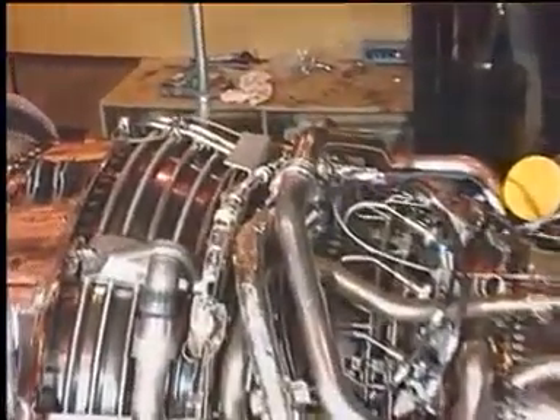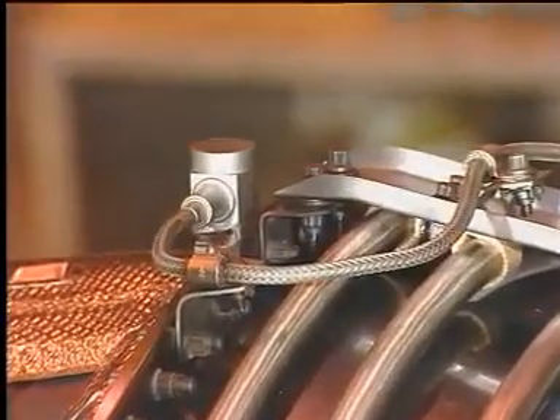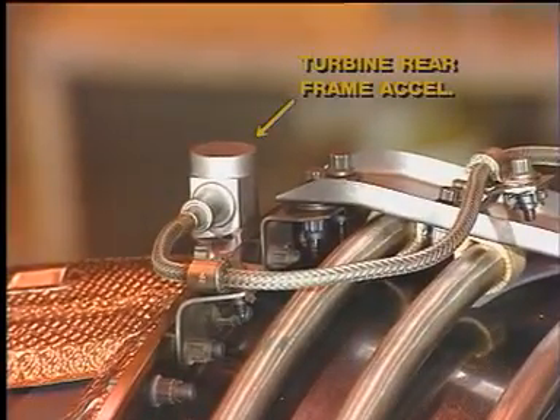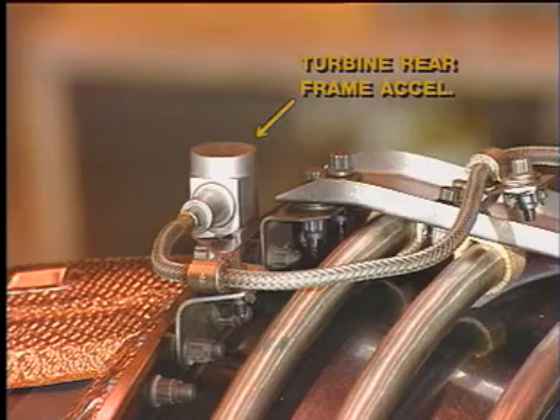And the second, located on the turbine rear frame, is used as a backup accelerometer in case of failure of the number 1 bearing vibration sensor, which is not line replaceable. This second accelerometer is also used with the first one for balancing purposes.